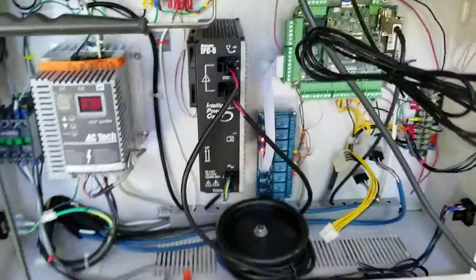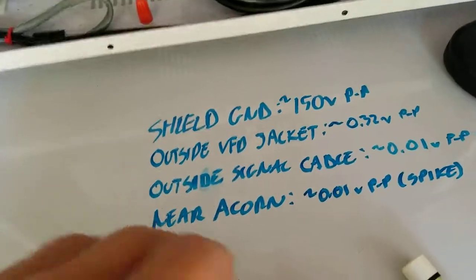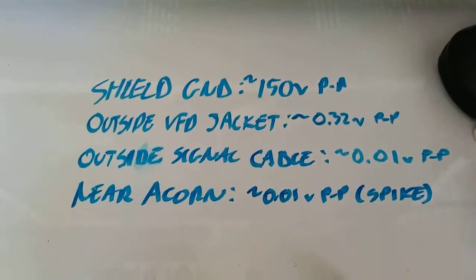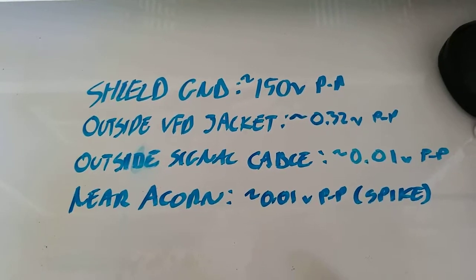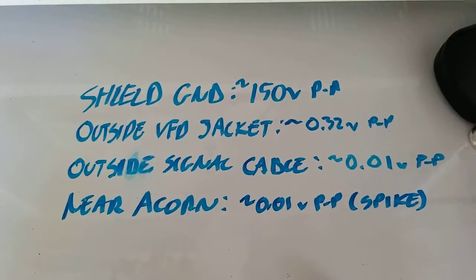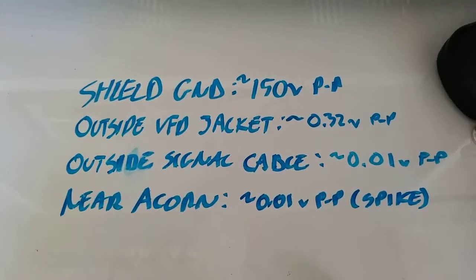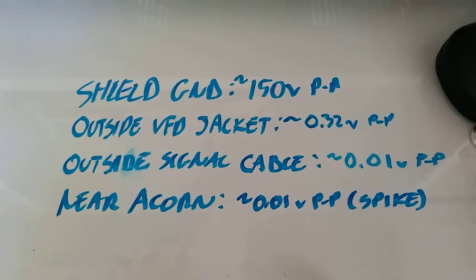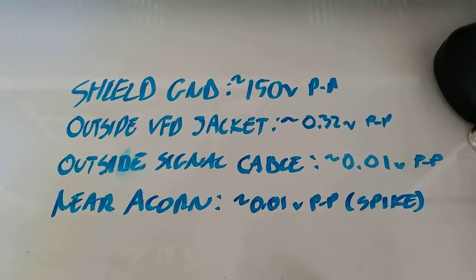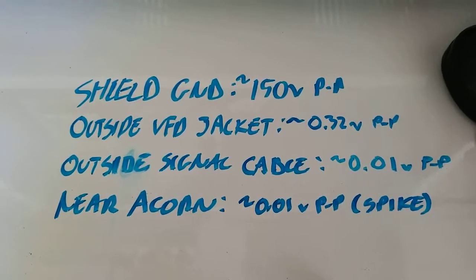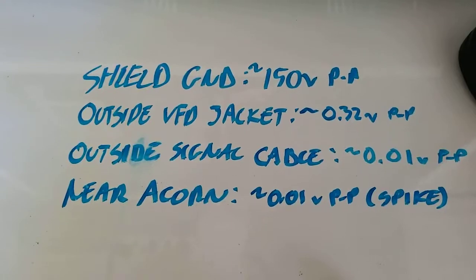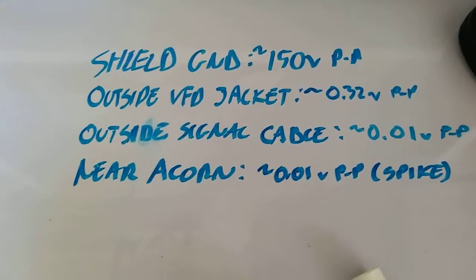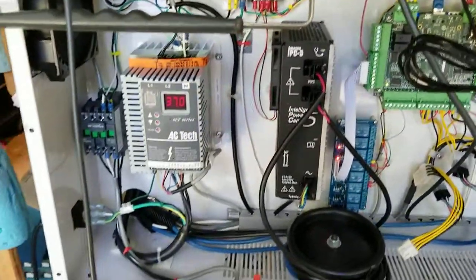So in the video, I just wanted to show what the effects are. I recorded this beforehand from some independent measurements. Again, the shield ground measuring a whopping 150 volts peak-to-peak. Outside the VFD jacket, 0.32. Near the signal cables, 0.01. And near the Acorn, 0.01, but just for that really short duration spike.